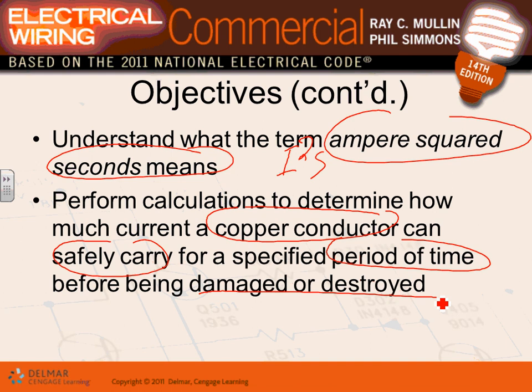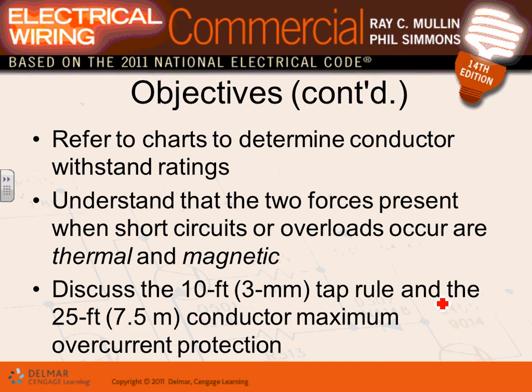Double the amount of current and it can carry it for a couple of minutes. Now make it 1,000 amps, and it can carry it for milliseconds, until the circuit breaker opens. If the circuit breaker does not open or the fuse does not melt, your conductor will start melting. That's the term they use: withstand rating for equipment, or damage curve for equipment or conductors. A big deal.